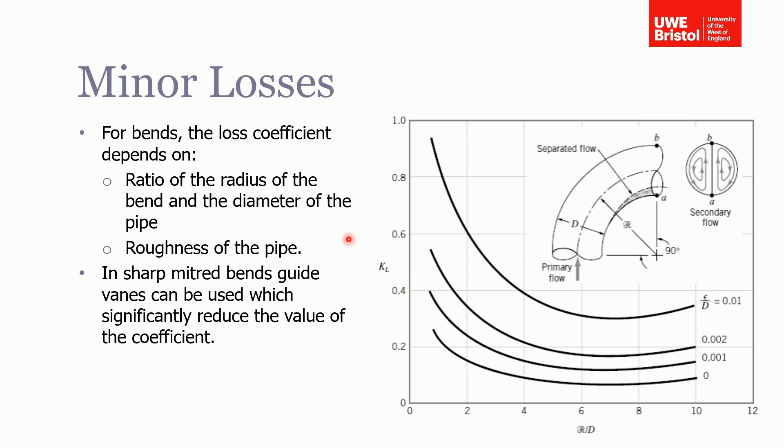So you can then use that to find out the pressure loss in this component, and particularly for sharp bends, if you want to reduce the pressure loss, then you can use guide vanes to help reduce the value of the loss coefficient.